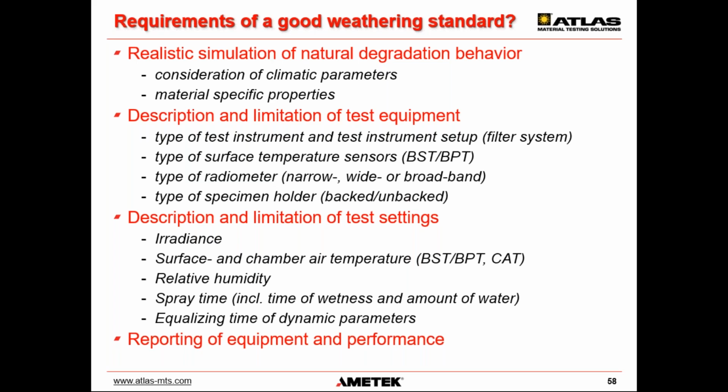With each of these limitations, you reduce the risk of inconsistent or variable weathering results. And this is why, as I mentioned before, instrument-based standards were typically more precise, because there was less variability because of one instrument design.